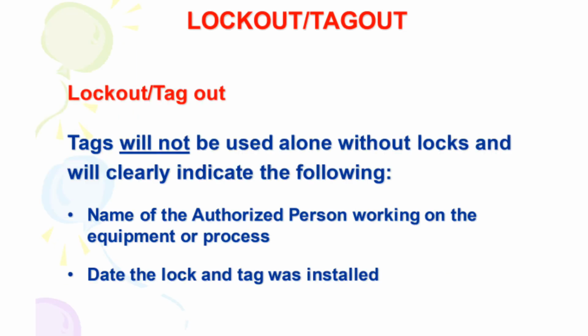Lockout Tagout. Tags will not be used alone without locks and will clearly indicate the following: the name of the authorized person working on the equipment or process, and the date the lock and tag was installed.